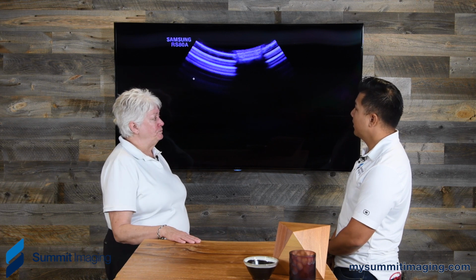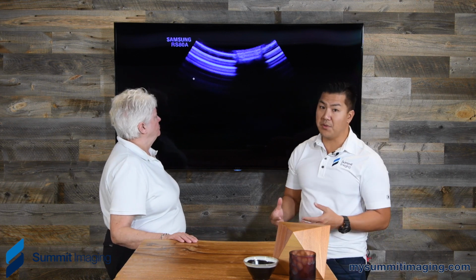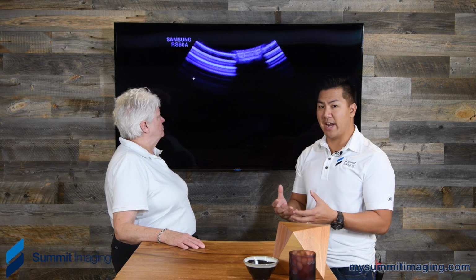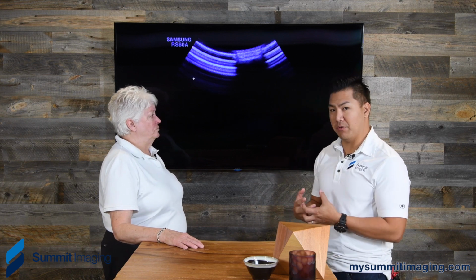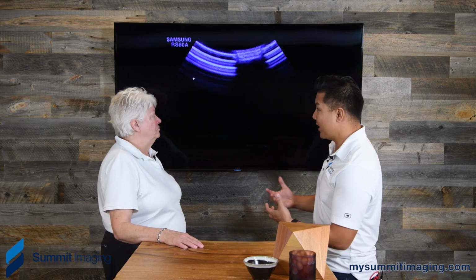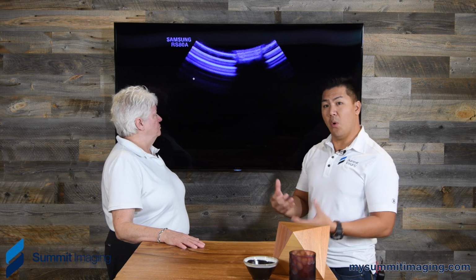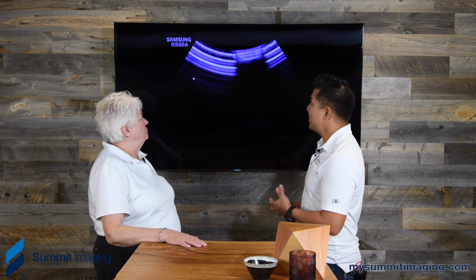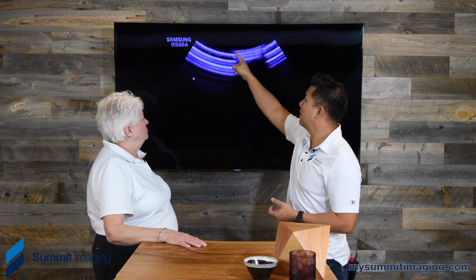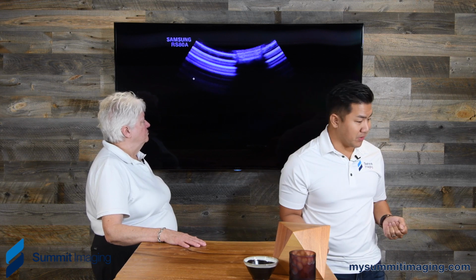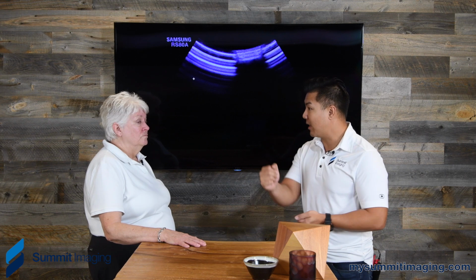Yeah. So what we're seeing here in this volumetric probe, because they're mechanical and sound doesn't travel through air very well to create an image, is that they're filled with oil. And what you're seeing here is actually an air bubble between the lens and the crystal, because there should be oil in between that. So oil has leaked out somehow. Maybe it was accidentally banged when somebody was rotating to put a probe away back onto the ultrasound machine. Could have been dropped.